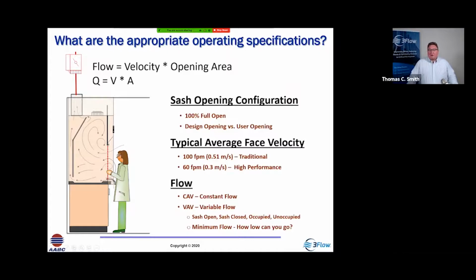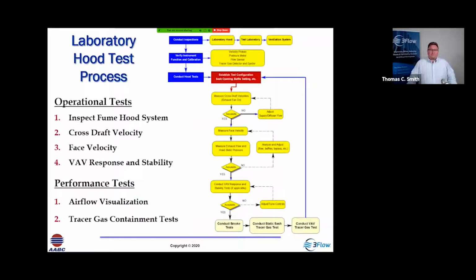Traditional hoods typically require 100 feet per minute, but a brand new high performance hood could go down as low as 60 feet per minute. So that's another question. What kind of hood do you have? And then if you have a VAV hood, how low can you go on the flow? When that sash is closed, how can we reduce that flow and how low can we go before it becomes a problem? We've got to maintain enough containment, and we have to dilute those materials, and we have to transport them out of the system. So the minimum flow becomes very, very critical.